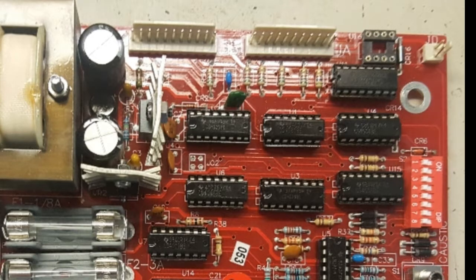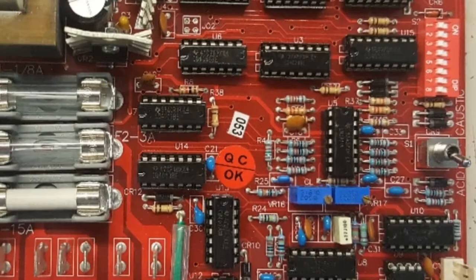Now, if you go right below the dip switches, there's an active toggle switch, depending on the circuit board you have, the red board or blue board. On the red board, it's just coming off of the side, and on the blue board, it's going to run vertical. And this is basically acid or caustic. Some of our Aquasol customers use a base, in which case that actually raises the pH. But for pool shore applications, they use acid. So you always want that in a down position on your body of water.